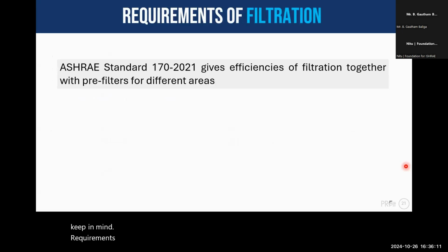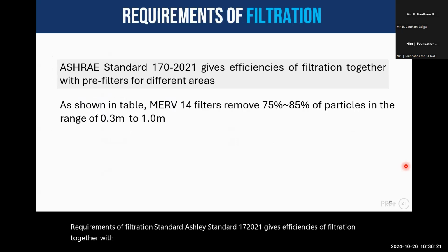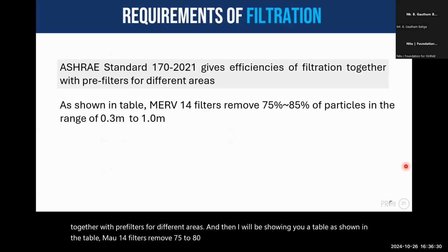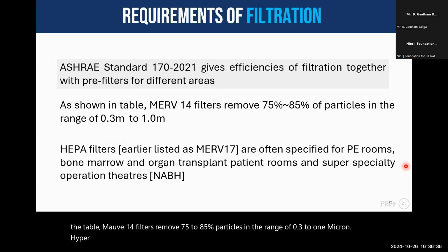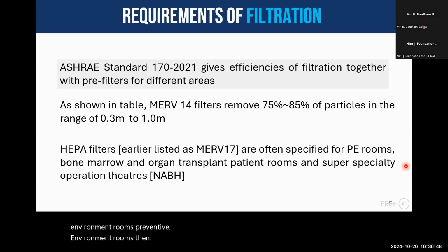Requirements of filtration. Standard ASHRAE standard 170-2021 gives efficiencies of filtration together with pre-filters for different areas. And then I'll be showing you a table. As shown in the table, MERV 14 filters remove 75 to 85% particles in the range of 0.3 to 1 micron. HEPA filters, earlier called MERV 17, are often specified in PE rooms, that is your positive environment rooms, protective environment rooms, then bone marrow and organ transplant patient rooms, super specialty operation theaters.